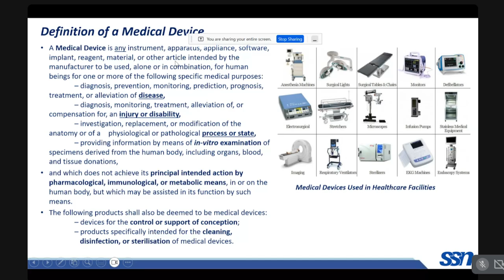Going forward, in regulatory terms, we have something called intended use and indications for use. Going back to the first slide, there is a statement that says intended by the manufacturer to be used alone or in combination for specific purposes, which could include diagnosis, prevention, monitoring, prediction, prognosis, or therapy. Intended use basically describes the high-level purpose of the device, what the device is intended for. For instance, the basic use of a glucometer is measuring glucose. And this intended use usually determines the class of the device.